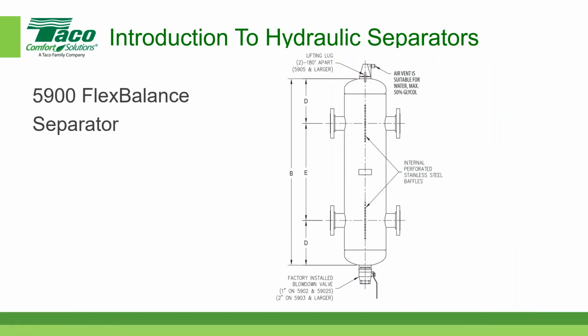And let's look at some dimensional information. If you remember what I said a few minutes ago, what's important here is all of the dimensional information. And it's critical to have the right overall height of this device, the distance between the connections, and then obviously the connections to the top and the connections to the bottom. So for a pre-engineered device, we figure out all of that stuff based on the size of the unit and how many GPM each one can handle.